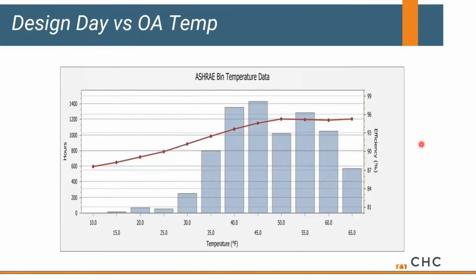One thing to think about, at least in Portland, is that the design day, a worst case scenario, might be 10 degrees. That might rise a little bit with global warming potential, but for a long time, it's always been 10 degrees. And we're going to design a boiler plant for that as our worst case scenario.